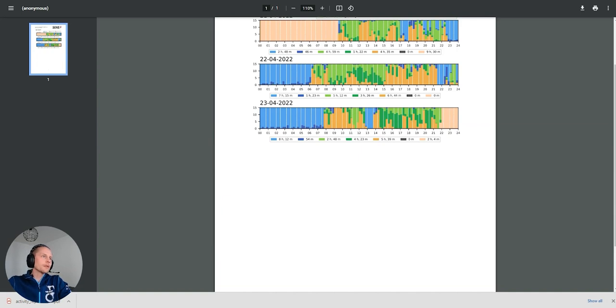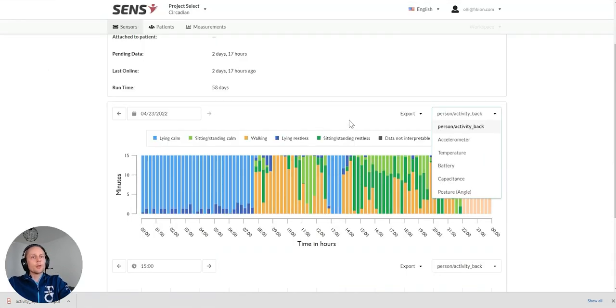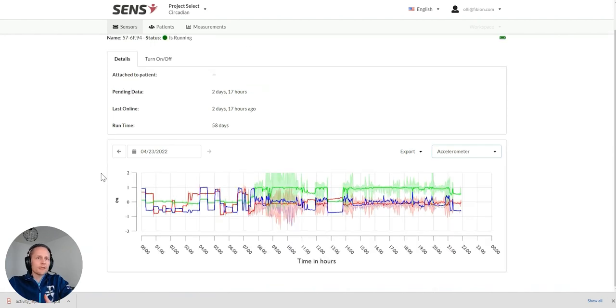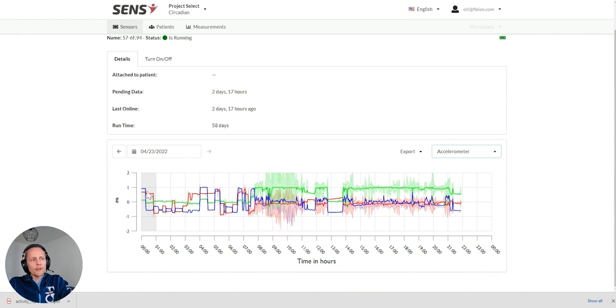So that's the export of the PDF report. And if we want to look also, the device is measuring 3-axis acceleration. If you want to look at the data more closely, you have X, Y and Z axis there.